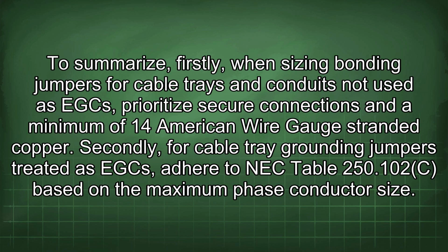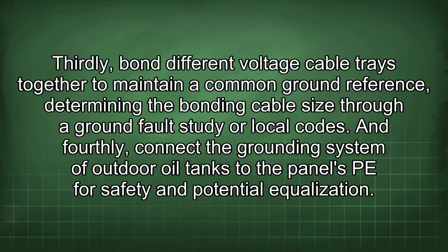To summarize, firstly, when sizing bonding jumpers for cable trays and conduits not used as EGC, prioritize secure connections and a minimum of 14 American wire gauge stranded copper. Secondly, for cable tray grounding jumpers treated as EGC, adhere to NEC Table 250.102(C) based on the maximum phase conductor size. Thirdly, bond different voltage cable trays together to maintain a common ground reference, determining the bonding cable size through a ground fault study or local codes. And fourthly, connect the grounding system of outdoor oil tanks to the panel's PE for safety and potential equalization.